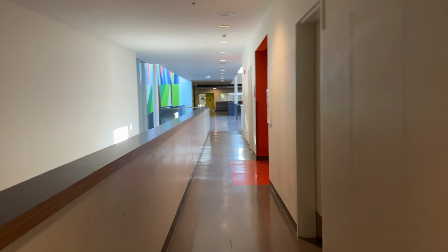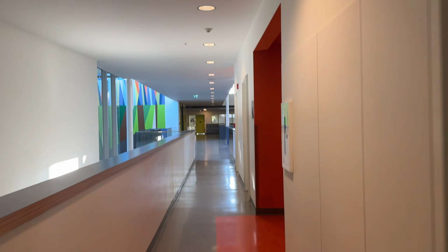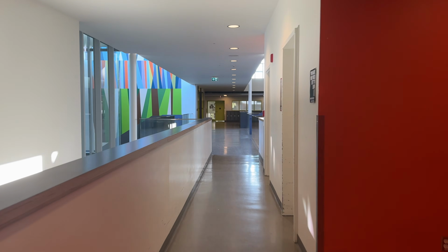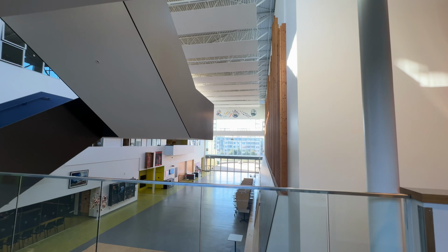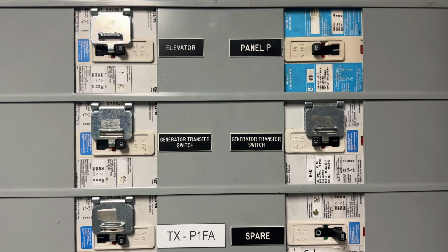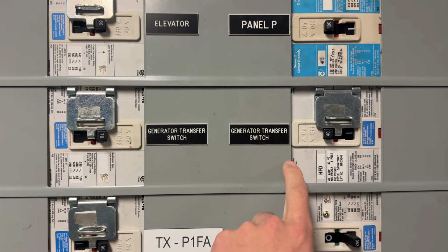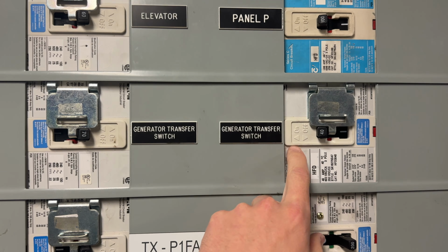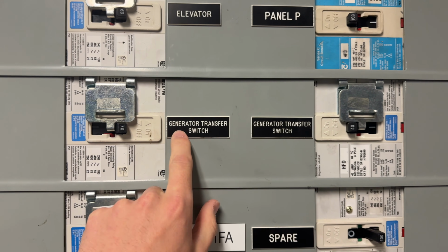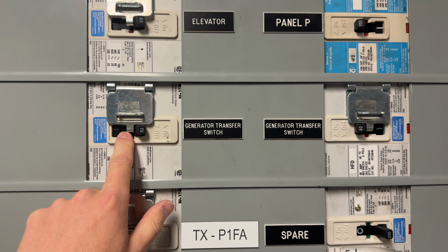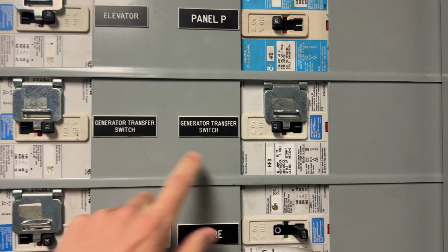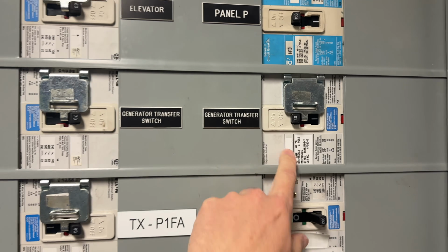That means classrooms don't need emergency lighting, but bathrooms do have it. And this big atrium here also has quite a bit of emergency lighting. So these are the two breakers we'll need to turn off. We have our generator transfer switch and our other generator transfer switch. Our 70 is the life safety. The 40 is the backup, general backup power.